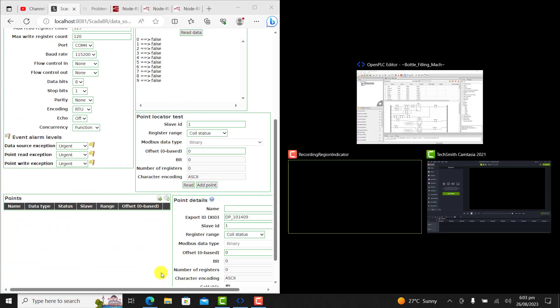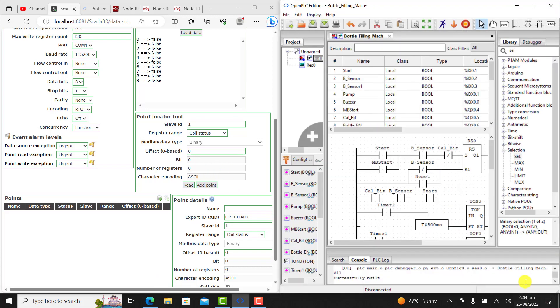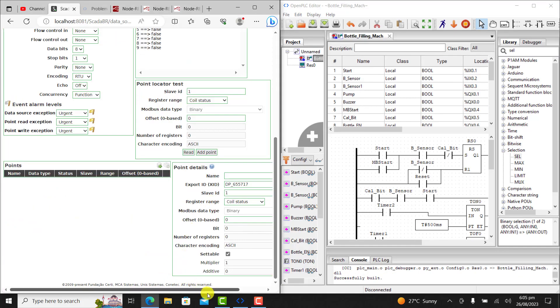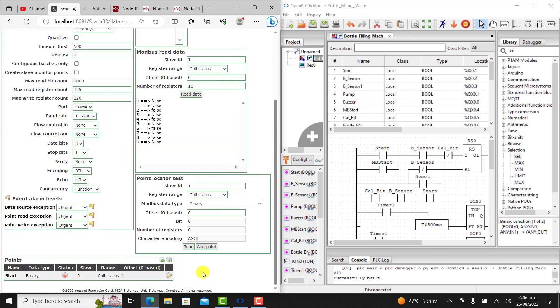Now I need to add my points, so I place the Open PLC editor side by side and look at the points. The first point I need to add — I click on the plus and then I add my stats tag. I call it Start. It's a coil, so it remains like that. The offset address is 4, so I put 4 right there. I click on save and my first tag is added.